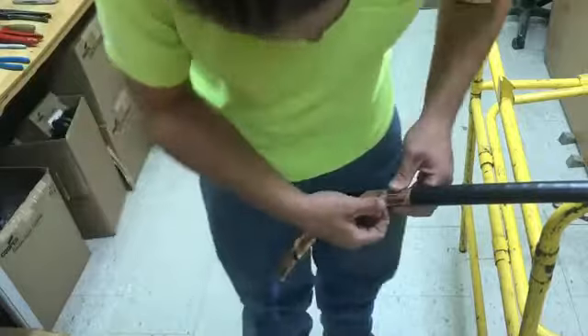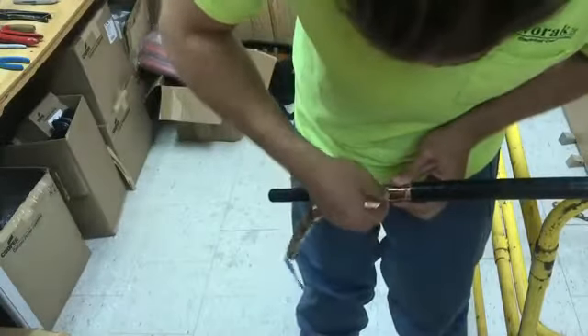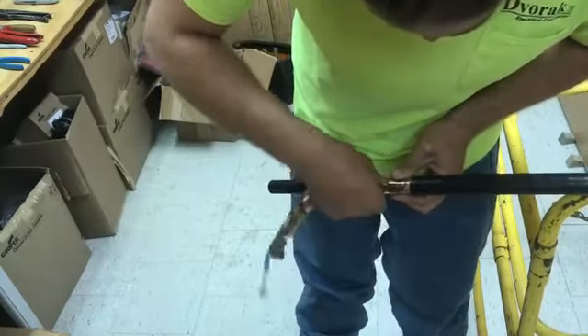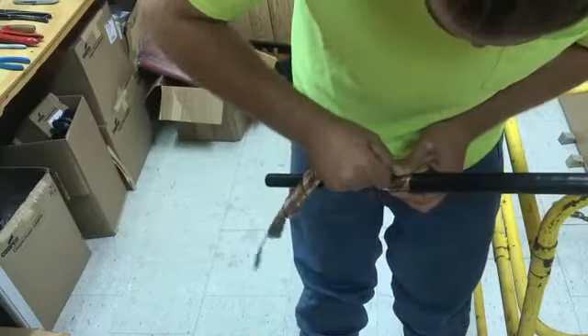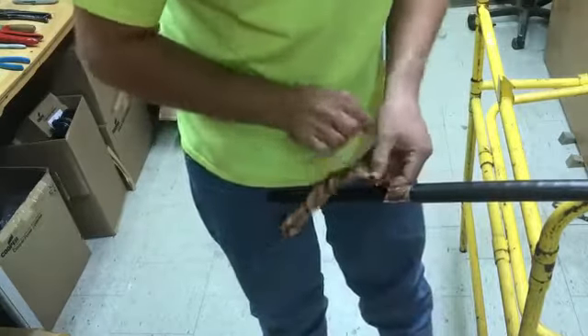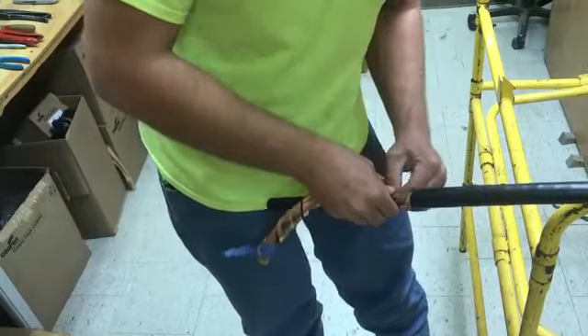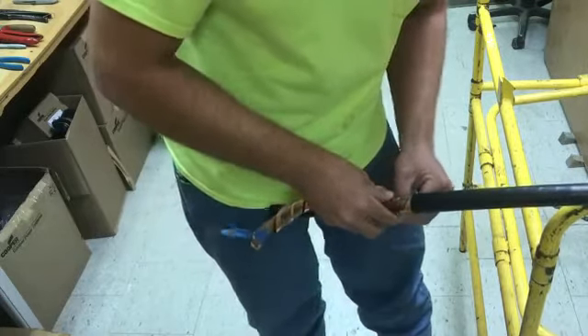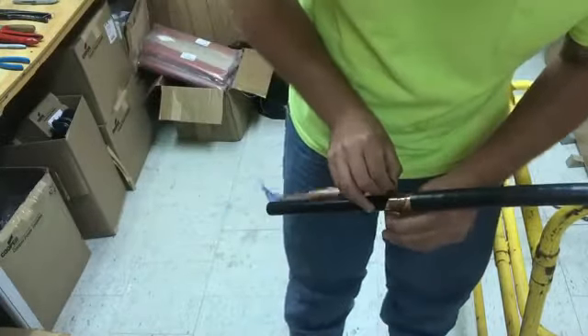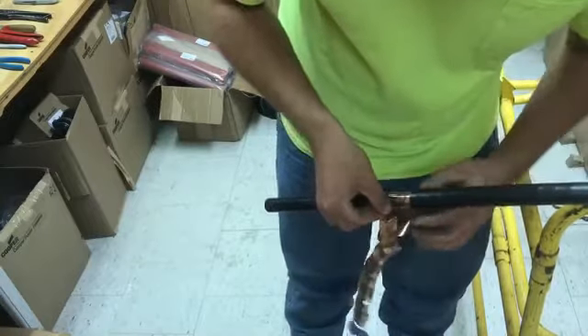I'll now remove the copper tape shield. There's 2 pieces of copper tape shield, so I'll do this both at the same time. I begin wiggling back using force against the constant force spring and tearing in a diagonal fashion and around the cable. This will leave a clean factory edge, and you do not have to use any cutting tools to do so.